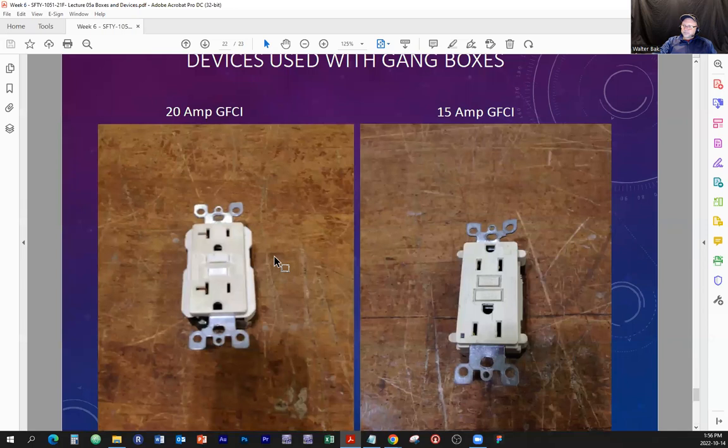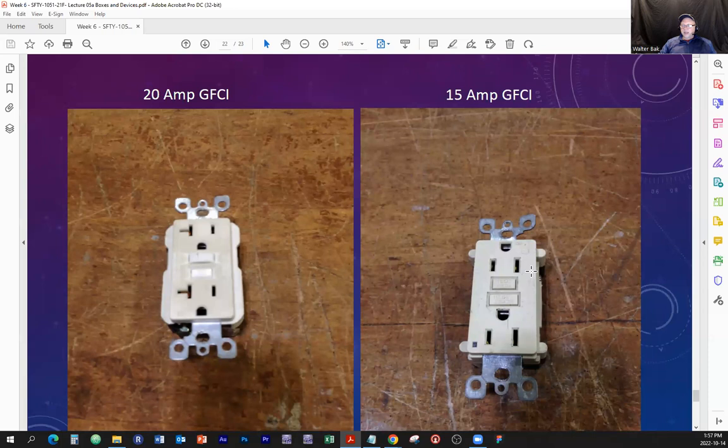We already talked about it in the morning, but let's talk about it again. It is important, so please stay with me right now. Okay, I'll get to the point. Let's say you have this 15 amp circuit installed not too far from the window, and you want to install a window air conditioner, and it has this plug, so you can't plug it into this. So what do you have to do? You're going to have to replace this receptacle with one that is rated for 20 amp.